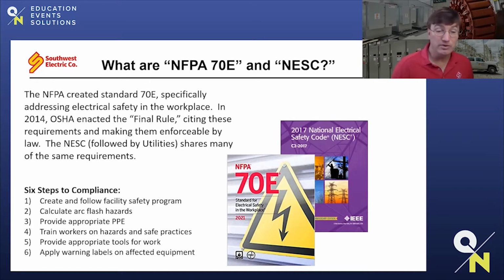These standards include these six steps of compliance that you see on your screen, and every facility is required to follow these compliance steps. It's very possible that most facilities have some kind of safety program, but not all facilities have calculated their arc flash hazards and their energies. Because they don't have these values determined, they may not have the proper personal protective equipment, or PPE, in order to protect their workers.